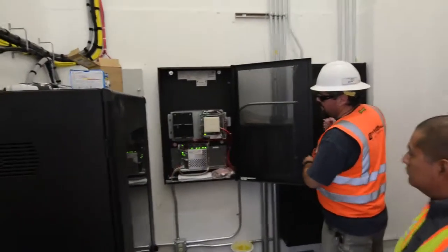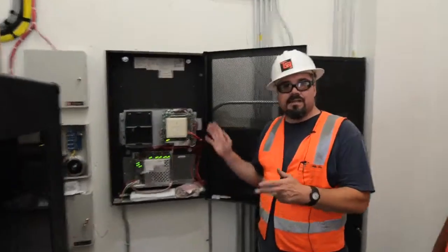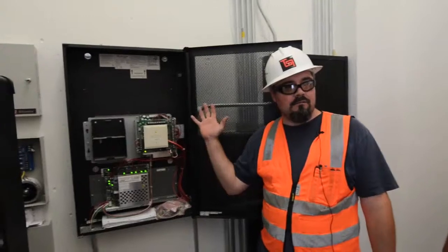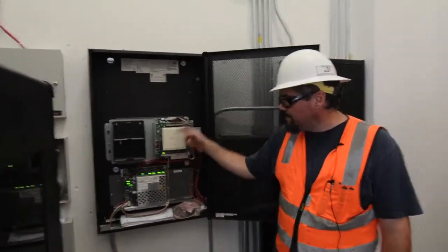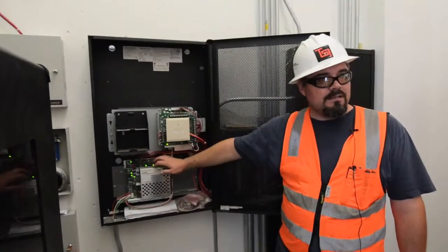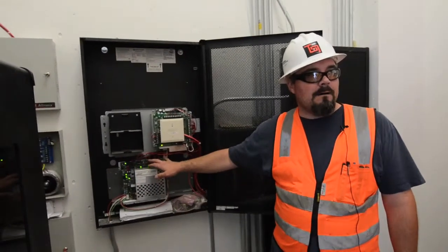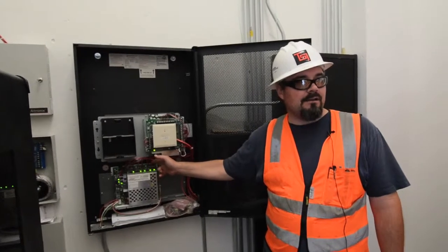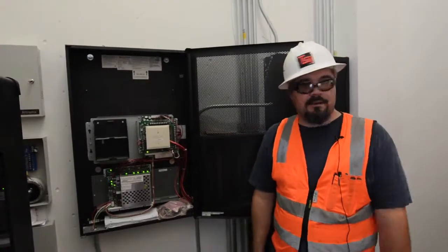This right here is going to be the power supply for the power for the sniffers. And so we sort of broke up the concourse in half. We consider this the east half. And so everything in the middle here will come here for power wise, all the relays and all the sniffers. These are all the power wires right here. This right here is also a power supply for multiple power runs. Now these are zones, so we have about, I think, 3 to 4 CNGs hooked up to one leg, one zone of power. So I don't have a power going to every one of them. We daisy chained, I think, 3 or 4 together.